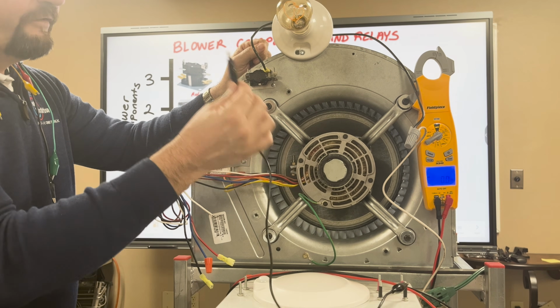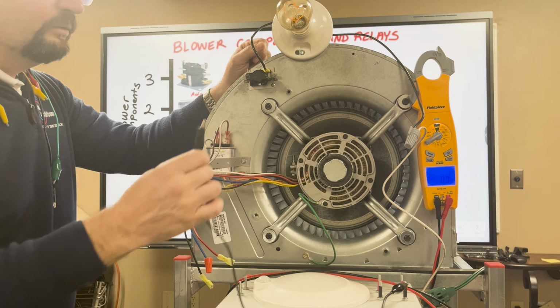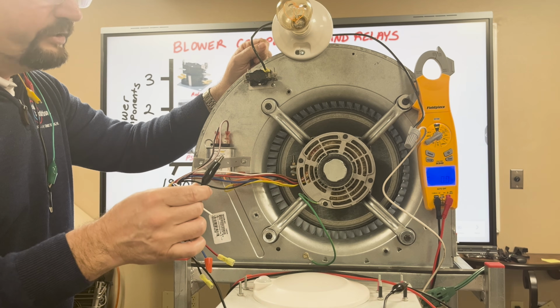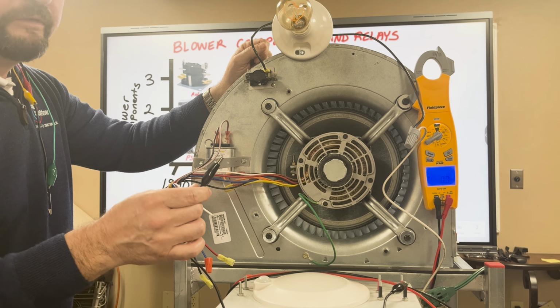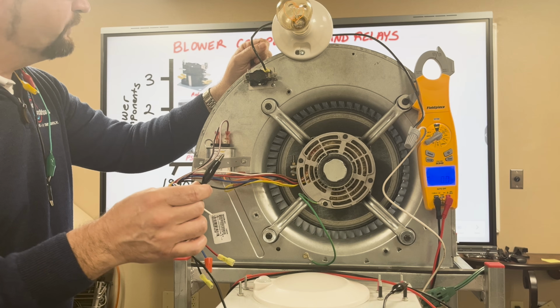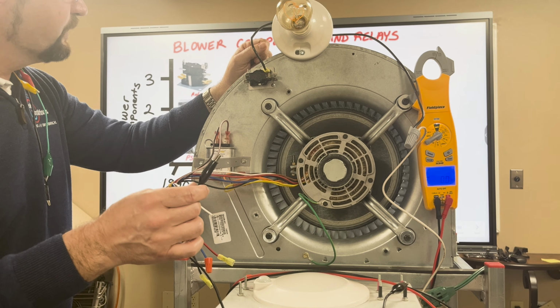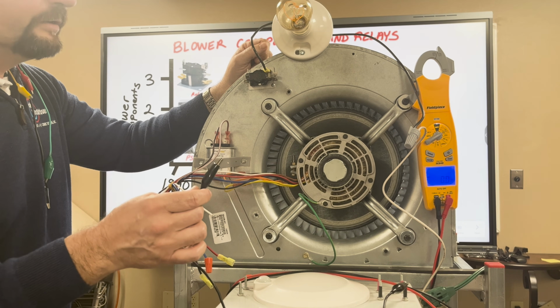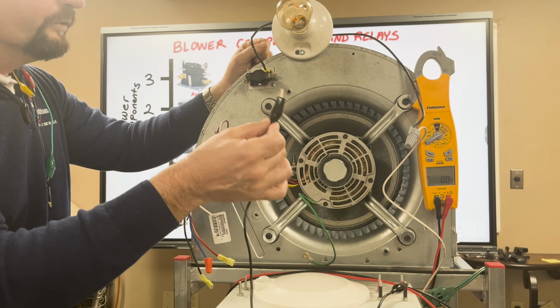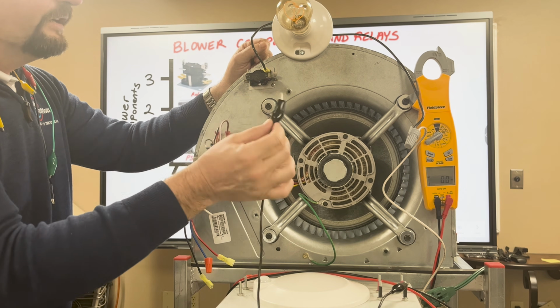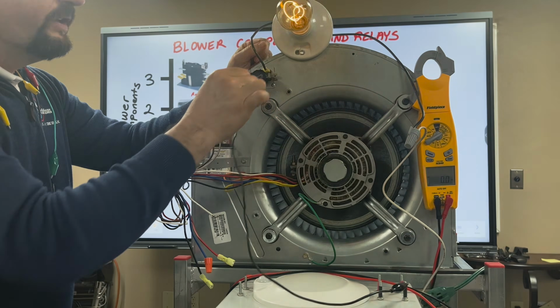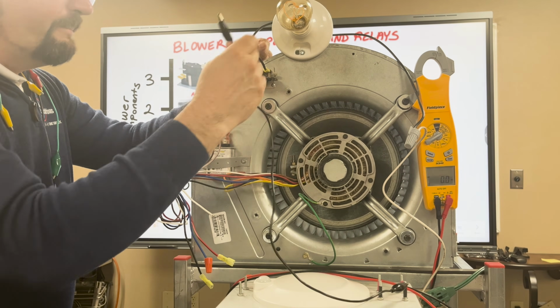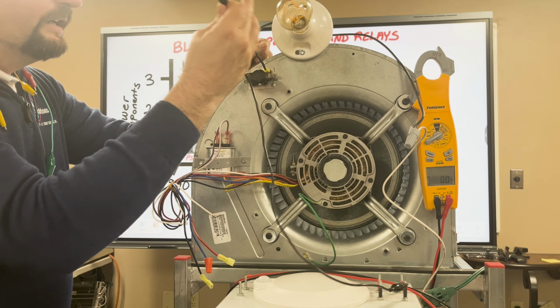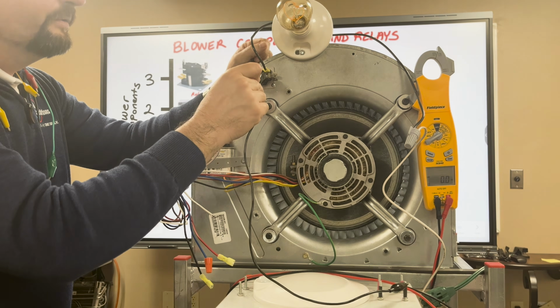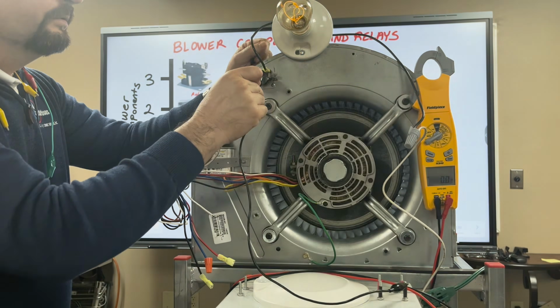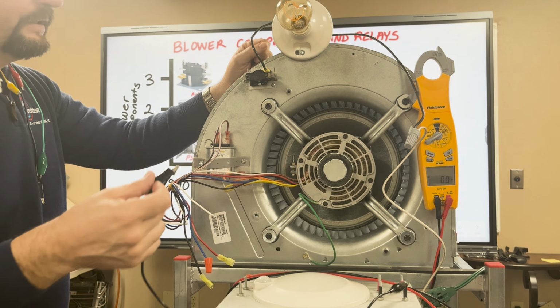Now if I were to take power and put it on that side, we're going to see a lot of smoke, a little bit of spark, maybe the lights might even go out in the room. Most likely the television behind us or the smart board behind us will definitely go out because we're plugged into that for neutral. But because I gave it power, that path back across there energized the load, as it was supposed to. There you go, and that's what that is.